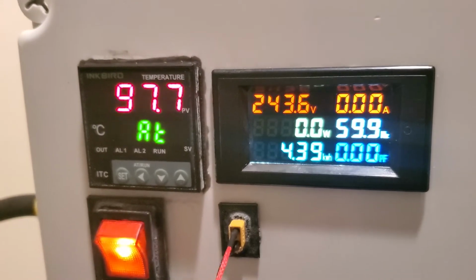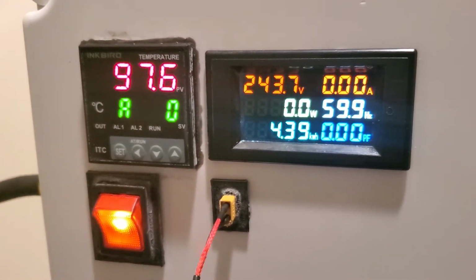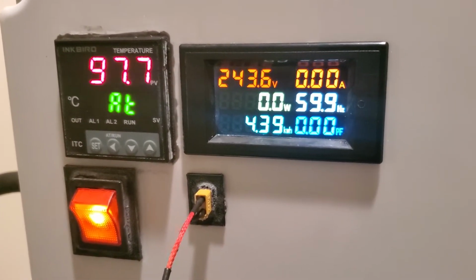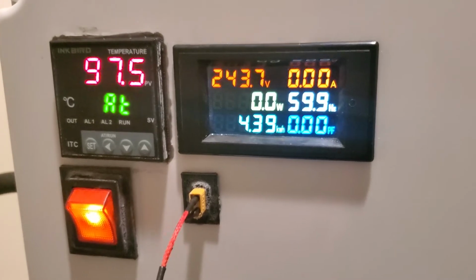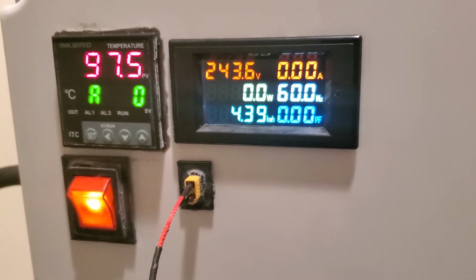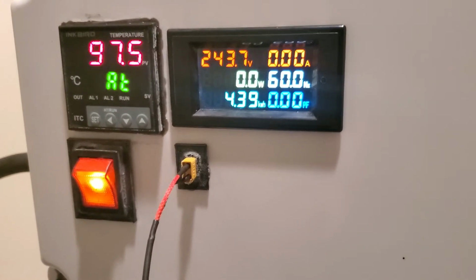However, that only works the first time you power the unit on. After that, you have to go into the setup of the controller to a parameter called CTRL, and that has to be set to option 2, and then the unit will enter the auto calibration mode.